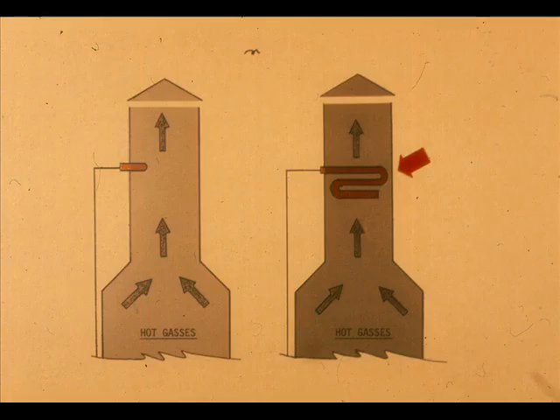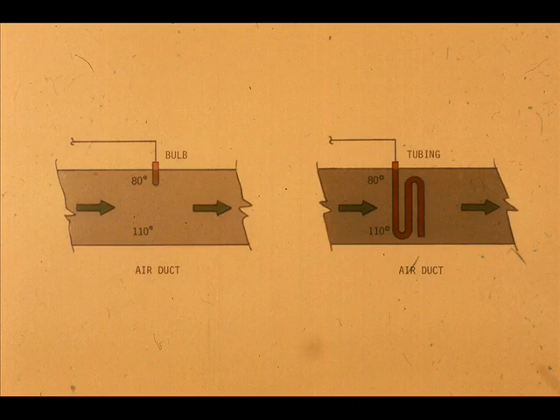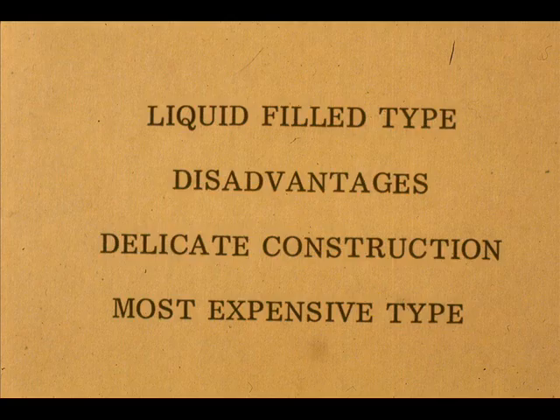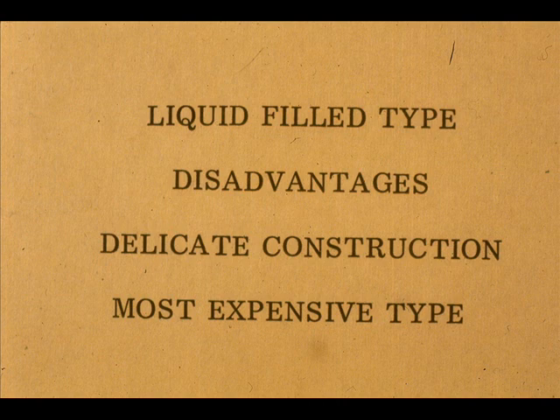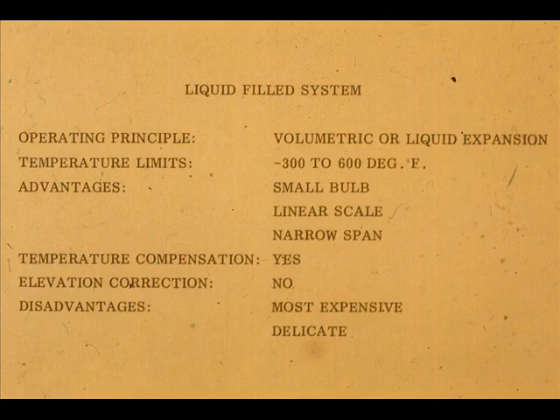Since liquid-filled systems measure average temperature, a length of tubing may be substituted for the bulb for fast response in air or gases. In some installations, such as large air ducts, this average reading is more desirable than a point reading. It is also more accurate. The disadvantages of the liquid-filled type are its delicate construction and its high cost. Here is a summary of the characteristics of the liquid-filled system.